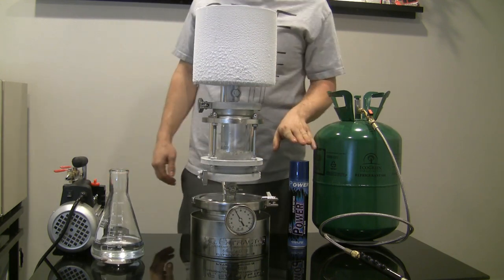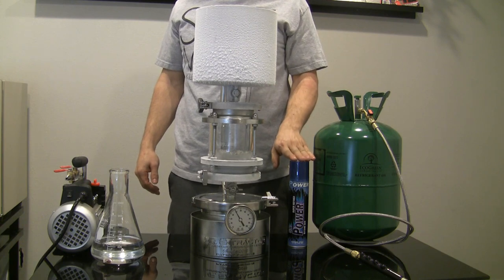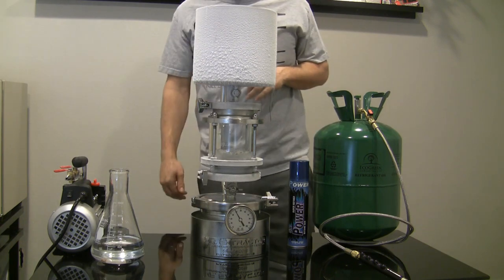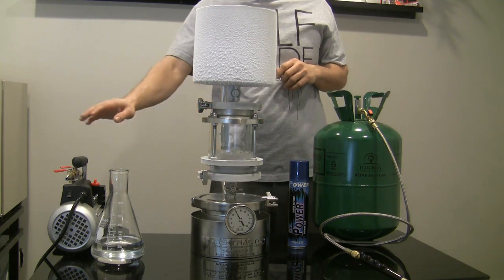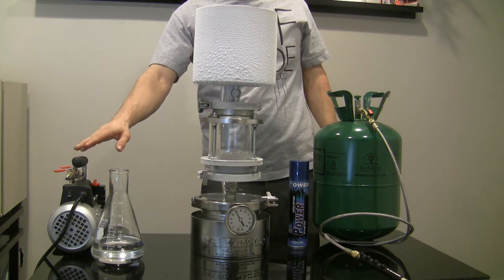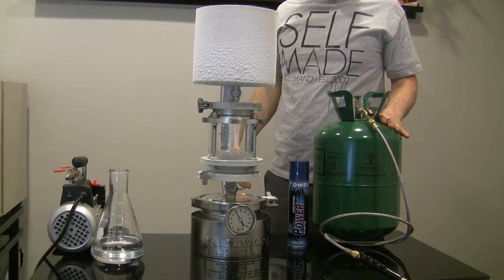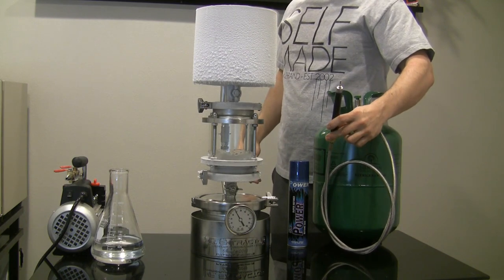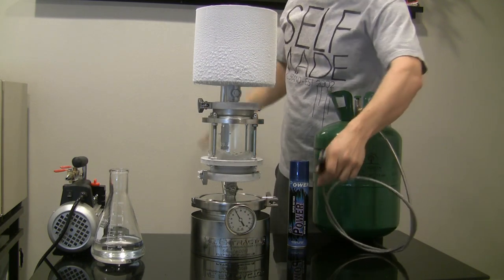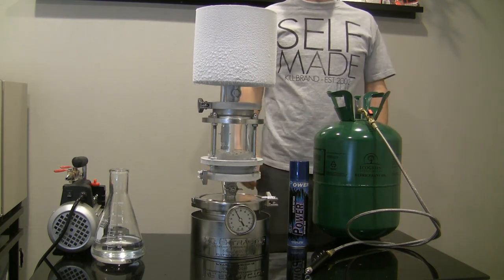In our previous videos, you watched us use Power 5 and easily accessible butane and not vacuum the system. We've upgraded the system to include a vacuum port. We have the unit vacuumed down right now, just using a simple, inexpensive vacuum pump. We've also got some laboratory-grade butane here. It comes with an adapter that we purchased that we were able to fill the device up with. So right now we have a vacuumed down device full of laboratory-grade butane.